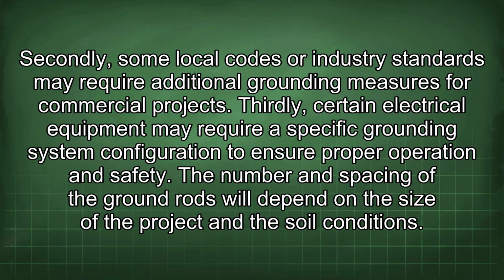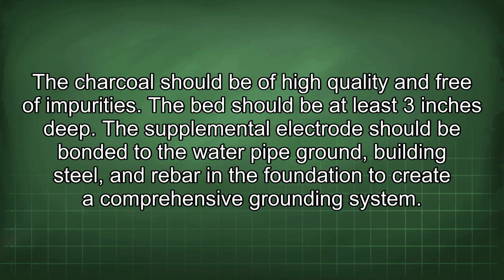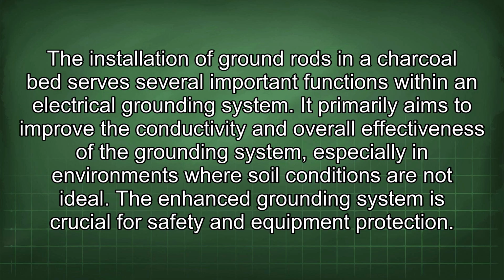The number and spacing of the ground rods will depend on the size of the project and the soil conditions. Charcoal should be of high quality and free of impurities. The bed should be at least 3 inches deep. The supplemental electrode should be bonded to the water pipe ground, building steel, and rebar in the foundation to create a comprehensive grounding system.